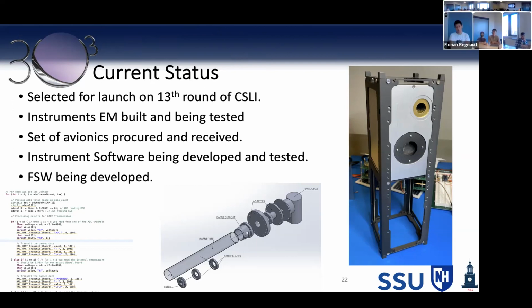And meanwhile, one thing we're trying to spend more time and effort on, compared to what you do on rockets, is calibration. Typically, instruments for rockets are not calibrated as carefully as for a CubeSat or space mission. So one thing that Kelly has been doing is developing the UV-PMT calibration protocol. I'm showing you in the middle the CAD of the PMT calibration. We have a UV source. I think we ordered some filters. We're supposed to have a calibrated photodiode, but there's no calibration for the next 6 months or more, 9 months or something like this. So we're going to have to make do with what we get.